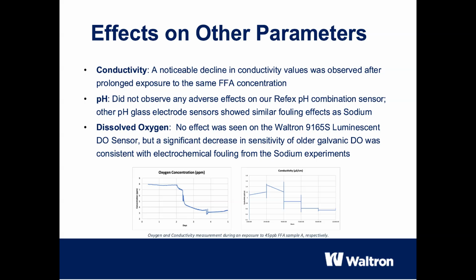Interestingly, some of our pH measurements showed no significant effects of contamination. However, we attribute this to the special chemical resistance of the Refex pH sensor we used, as other pH sensors were generally not immune and displayed similar results as the sodium. We saw a mixed picture with dissolved oxygen. Waltron's modern luminescent sensor showed zero degradation. An older galvanic oxygen sensor, however, showed a significant decrease in sensitivity, consistent with the observations of electrochemical fouling in the sodium tests. This underscores that electrochemical sensors in particular are vulnerable to FFA fouling.